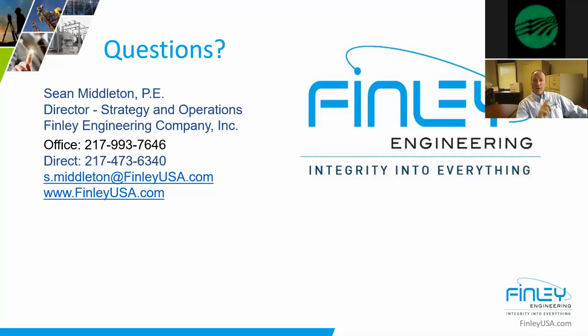And there are some devices, I mean, I can imagine if you're at 69 kV level, everything's going to be expensive. But could there be some kind of direct transfer trip communication methodology, where you would have fault sensing capability at the substation, probably at the transformer, that could then trip a device based on those signals and take it off so it can't contribute? I just wonder if that might be a cheaper way to mitigate.